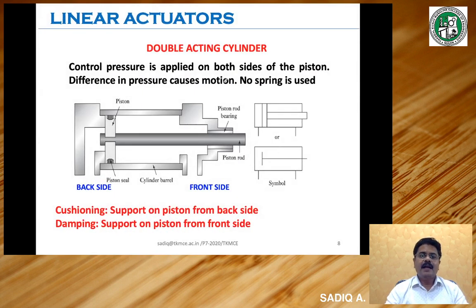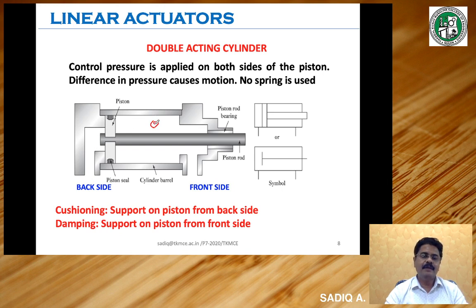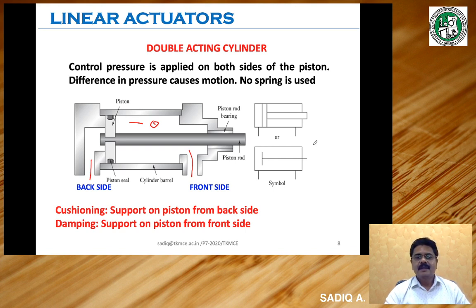In a double acting cylinder, control pressure is applied on both sides of the piston, and the difference in pressure causes motion. No spring is used because to-and-fro movements are done by control pressure. In the schematic diagram, the back side and front side are visible. When control pressure comes from one side, it pushes the piston against the fluid pressure on the other side. To-and-fro movements are possible by pressure supply from either side. The notation for a double acting cylinder shows a rectangular cylinder with two lines on either side of the piston.